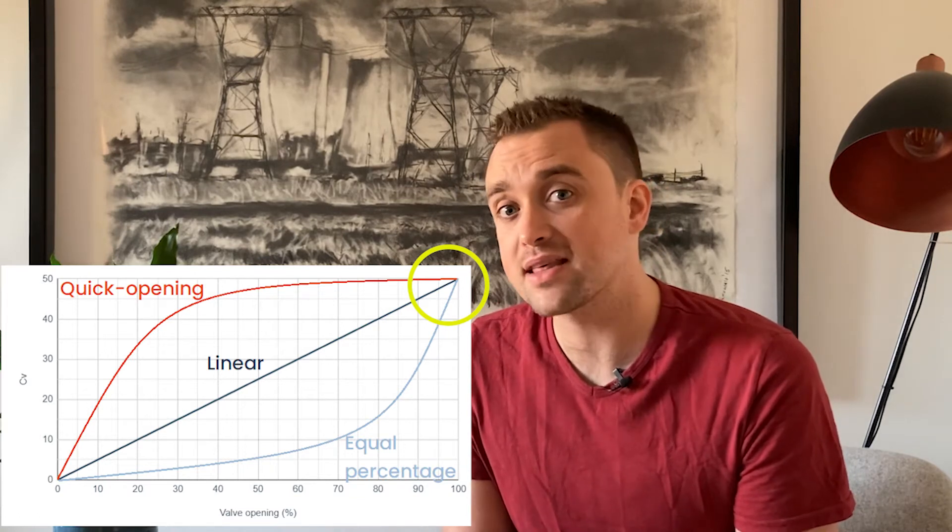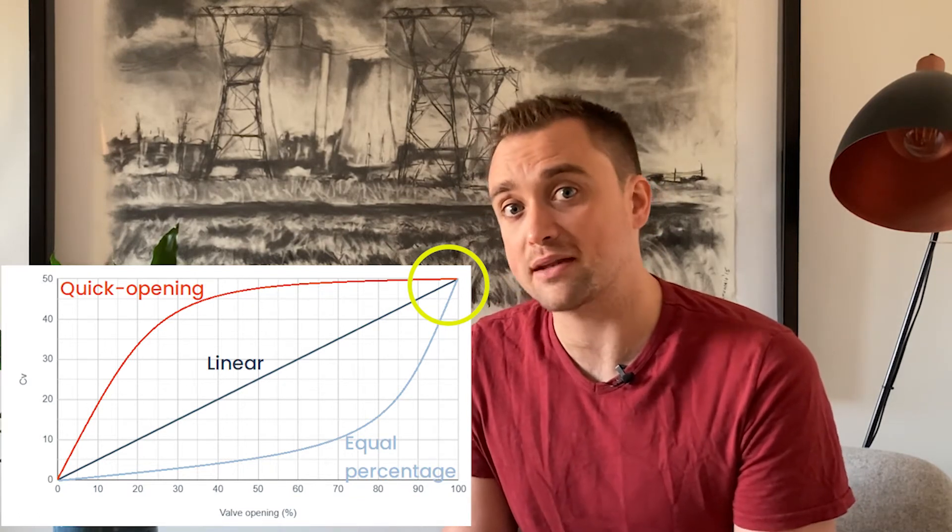The thing I find a little bit inadequate is an explanation of why this is the case, because it's not as if these valves take these different paths by coincidence. They are designed, meaning the internal structures of the globe and the seat are precisioned to give you that kind of response. We want them to do that.